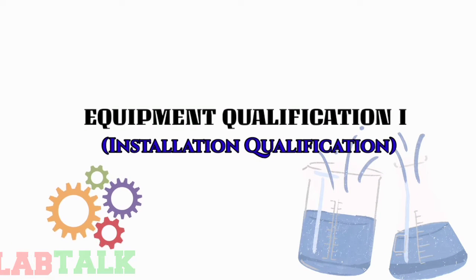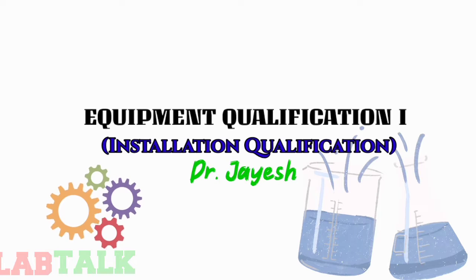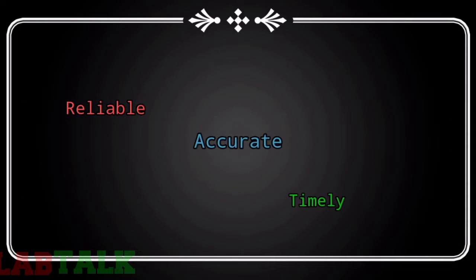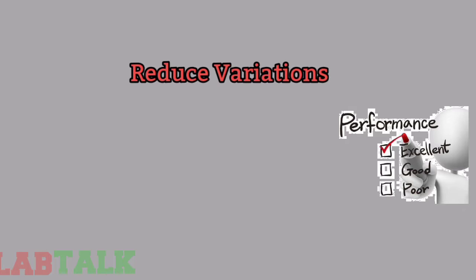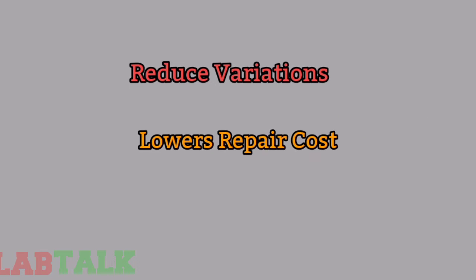Equipment management is one of the essential elements of a quality management system. Proper management of the equipment in the laboratory is necessary to ensure accurate, reliable and timely testing. The benefits of a good equipment management program are many. It helps to maintain a high level of laboratory performance, it reduces variation in test results and improves the technologist's confidence in the accuracy of testing results. It lowers repair costs, as fewer repairs will be needed for a well-maintained instrument.